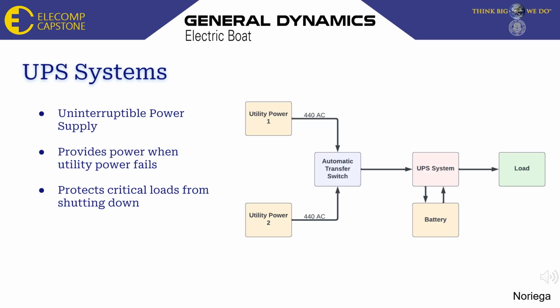A UPS is an uninterruptible power supply, and its main function is to provide a safeguard against power failures. These are a key part of a data center as they protect critical systems from shutting down abruptly and potentially corrupting data. To the right is a system where two power feeds run through a transfer switch and into a UPS, which charges the battery and provides power to the load.